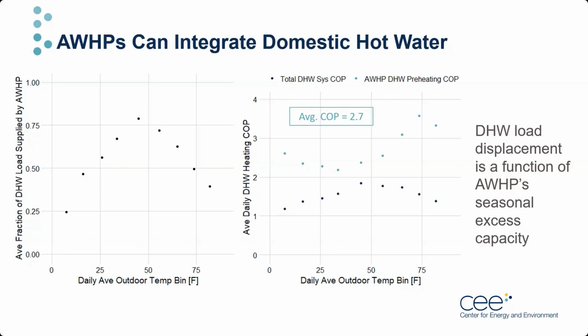Note that for this particular site, it had about 2 times the average domestic hot water load compared to the average single-family home in Minnesota. Here, the domestic hot water COP accounts for only the periods of time where the system was actively heating the domestic hot water. It does not include standby losses or all losses from reverting back to cooling mode in the summer. Instead, it is more representative of the average COP for all DHW preheating cycles that occur in a day.